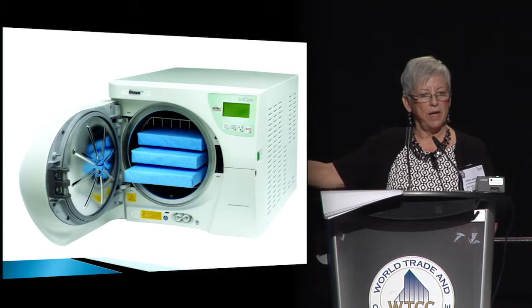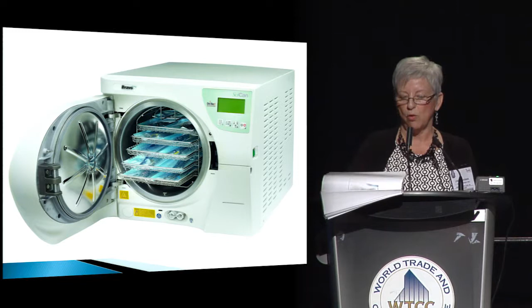This here just shows some peel pouch packages. These are laid flat, but in one layer, they're not stacked. And with peel pouch packages, what's really important is that they're so misused out there. They're only made to hold maybe one or two instruments, not 10 or 15, just one or two, and they need to be situated in these sterilizers so that the steam and air can still move around them and dry them properly. Because if the package comes out wet, it's not sterile. You'd have to reprocess the whole package.